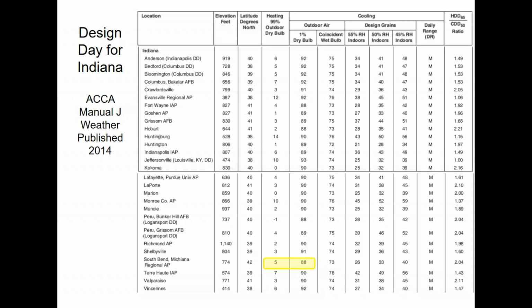So for South Bend, the heating design temperature is 5 degrees. If you're using 0 or you're using -5 or -10, you are not even relatively close. Does that mean it's never below 5 degrees in South Bend? No, of course it can get below 5 degrees in South Bend. But statistically, it's not below 5 degrees very many hours.